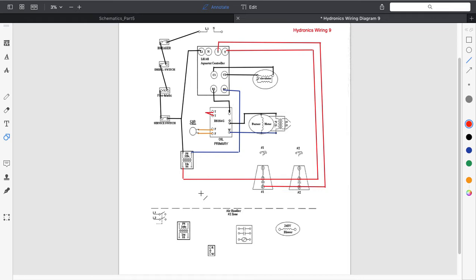Now, what about pin 1 on the zone valves? Remember, pin 1 is the W wire off the thermostats. So we're going to feed our thermostats from the secondary side of the transformer. So that takes care of that portion of the circuit.